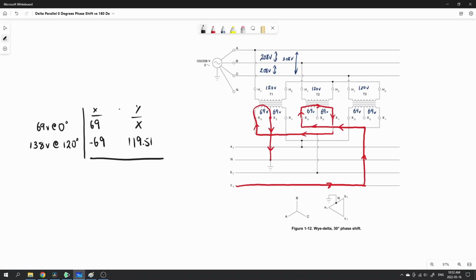So when we do the net voltage between these guys, 69 minus 69 is 0, and this is basically 0 plus 119.51. So the net voltage between these two windings here is basically 120 volts from C to neutral. So it seems like by finding these voltages by going through almost like a buck boost connection, we keep coming up with the appropriate values. So A to neutral was 69, B to neutral was 69, and now C to neutral is the vector sum of these, 138 and 69, giving us 120 volts from C to neutral.